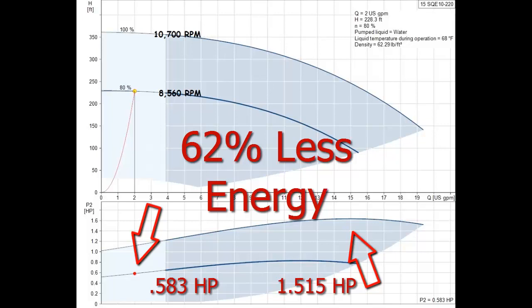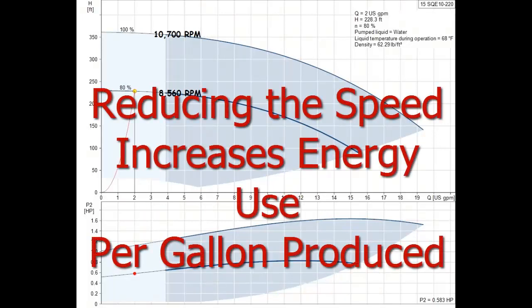But wait a minute, not so fast. Decreasing the speed only reduces the horsepower needed to spin the pump and motor. Varying the speed actually increases the energy consumption per gallon produced.